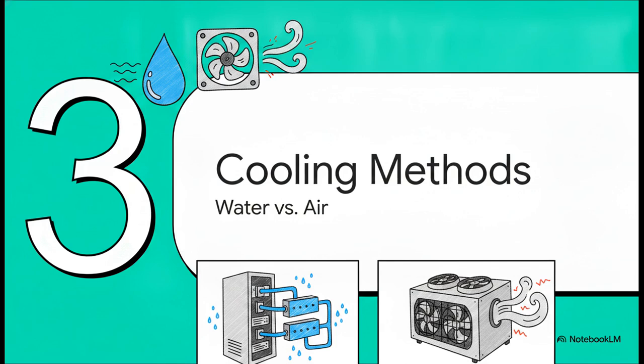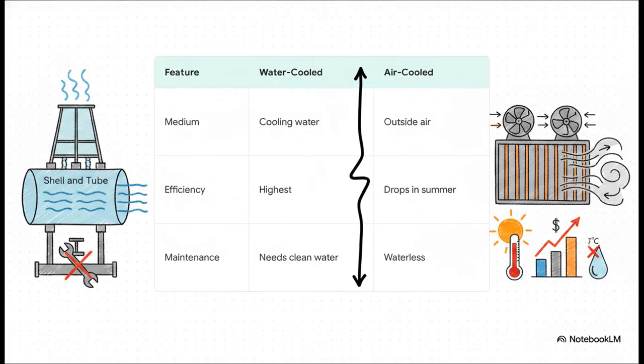Let's head into Section 3: water-cooled versus air-cooled. What's really interesting here is how exactly we reject that heat. Data center engineers basically have a massive choice between two main approaches. On one side, you've got water-cooled shell and tube condensers—hot gas hits tubes filled with cold water. Because water is absolutely brilliant at absorbing heat, this gives you unmatched energy efficiency. But it demands massive amounts of water.